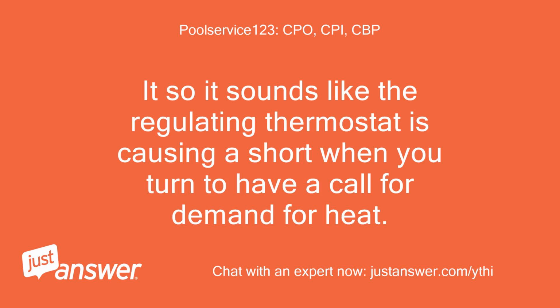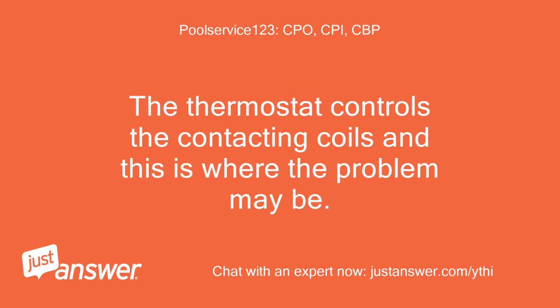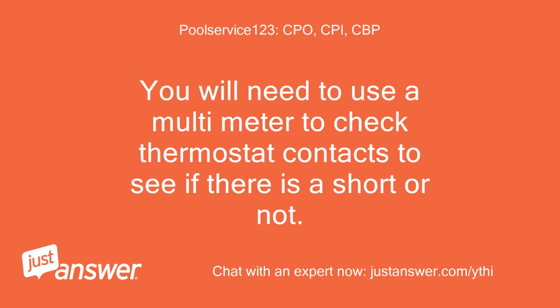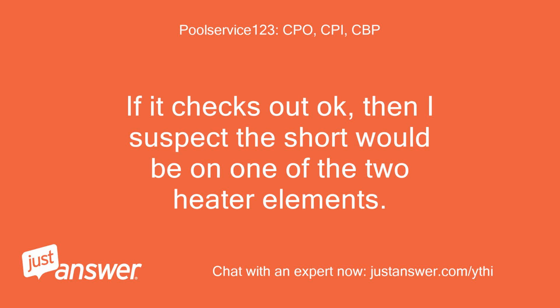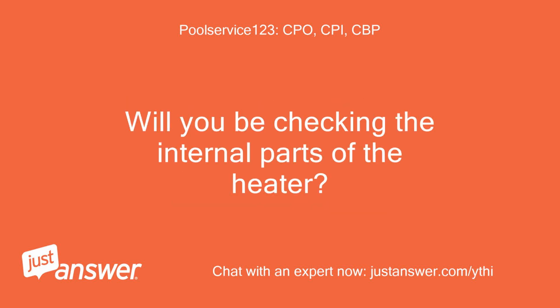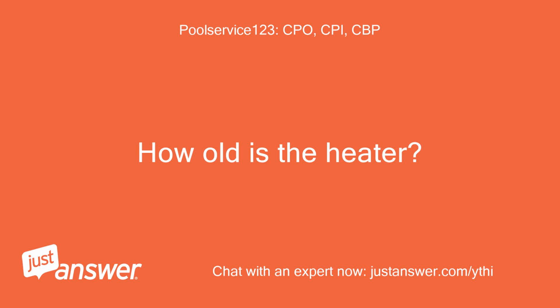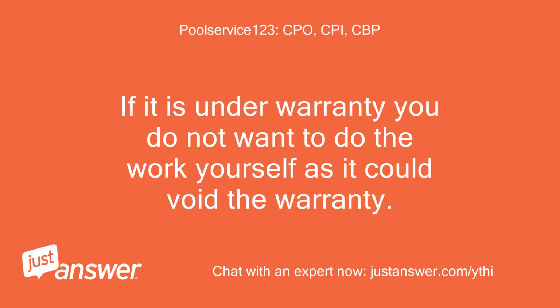It sounds like the regulating thermostat is causing a short when you turn it up to call for heat. The thermostat controls the contacting coils, and this is where the problem may be. You will need to use a multimeter to check the thermostat contacts to see if there is a short or not. If it checks out okay, then I suspect the short would be on one of the two heater elements. Will you be checking the internal parts of the heater? How old is the heater? If it is under warranty, you do not want to do the work yourself, as it could void the warranty.